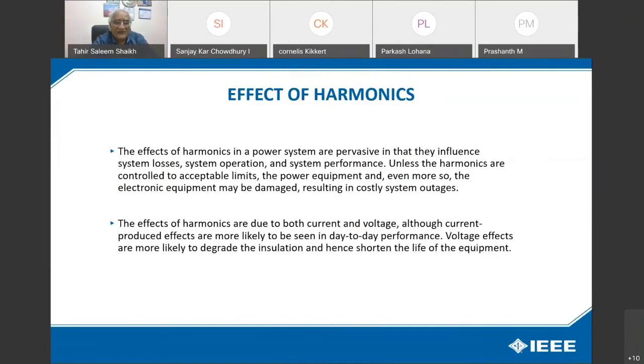The effects of harmonics in a power system are pervasive in that they influence system losses, system operation, and system performance. Unless the harmonics are controlled to acceptable limits, as described by the IEEE and IEC standards, the power equipment and even more so the electronic equipment may be damaged, resulting in costly system outages. The effects of harmonics are due to both current and voltage, although current produced effects are more likely to be seen in day-to-day performance. Voltage effects are more likely to degrade the insulation and shorten the life of the equipment.